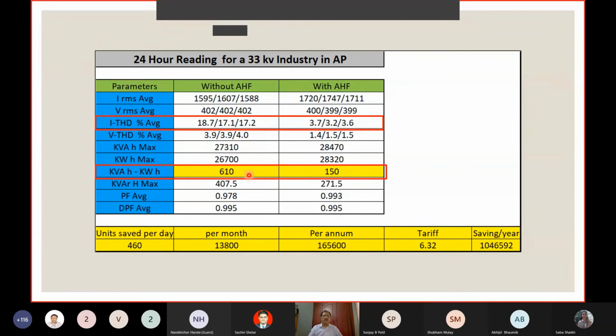So this is based on that, but I have given you a shortcut here. 610 units was the difference between kVAH and kWh each hour. After the active harmonic filters were installed, the harmonic came down to less than 4%. And the number of unit difference, you cannot make it 0, it came down to approximately 460 per hour. So from 610 it came down to 150. So this 460 gives you a cost saving at rupees 6.32 tariff of about 10 lakhs per annum.